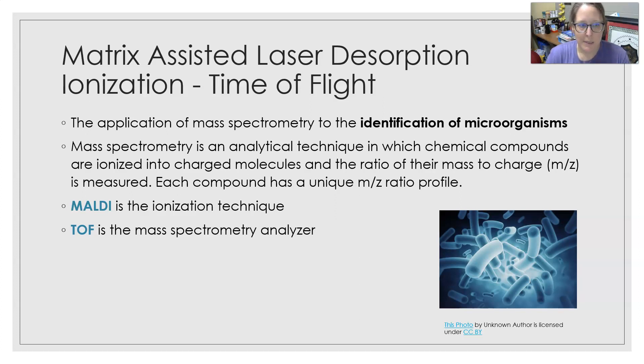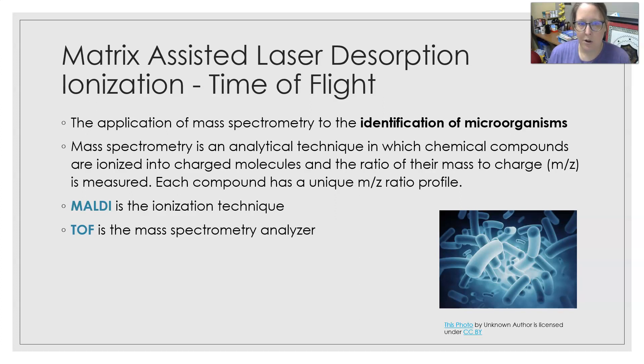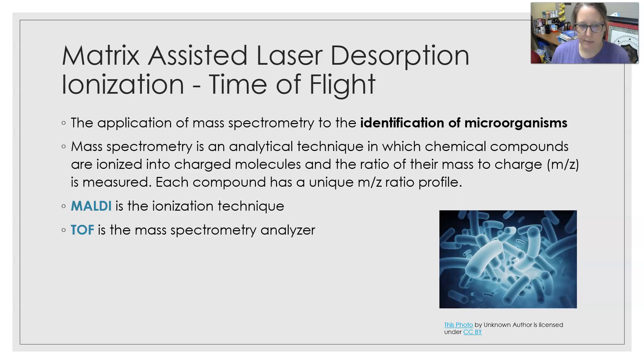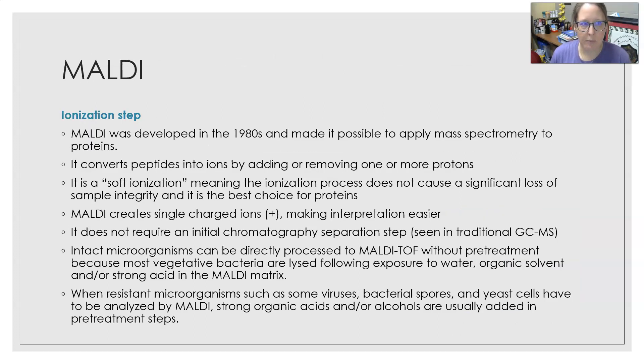Mass spectrometry is an analytical technique in which chemical compounds are ionized into charged molecules and the ratio of their mass to charge is measured. Each compound has a unique mass to charge ratio profile. In MALDI-TOF, MALDI is the ionization technique, and TOF — Time of Flight — is the mass spectrometry analyzer.